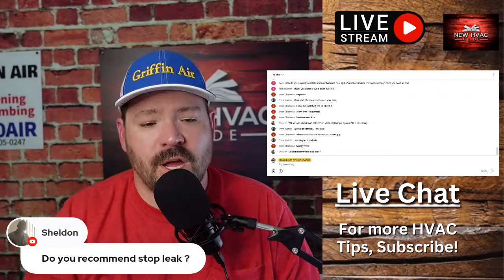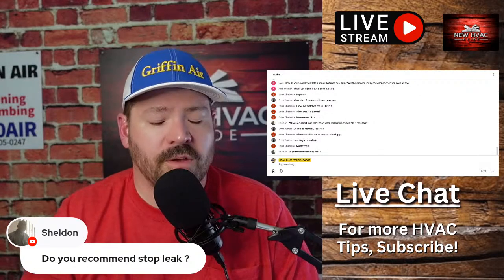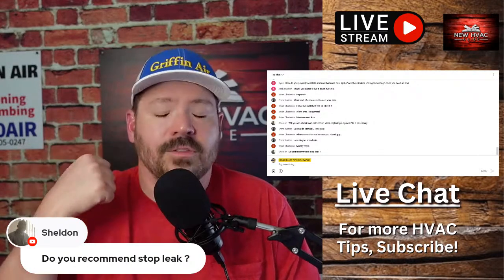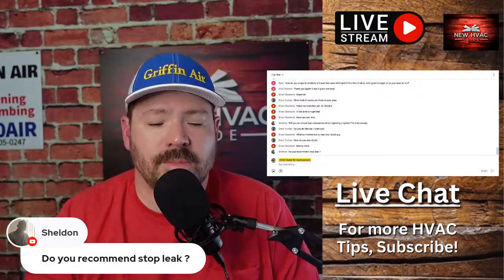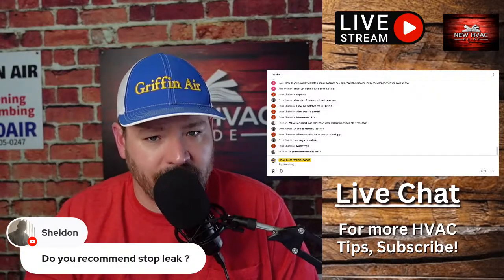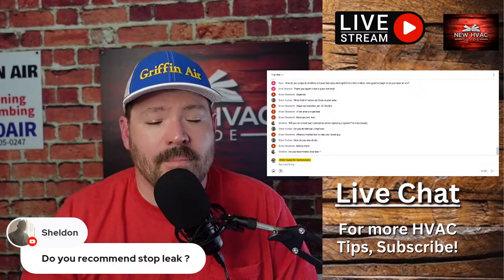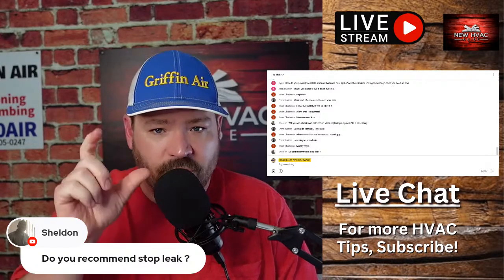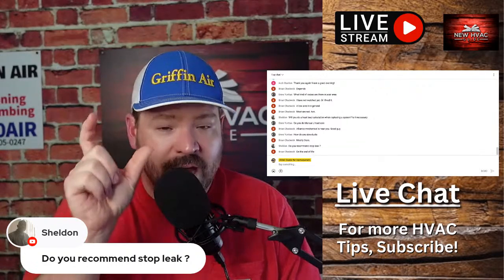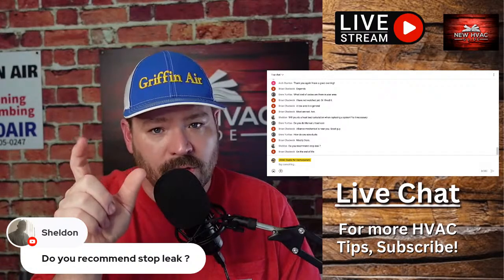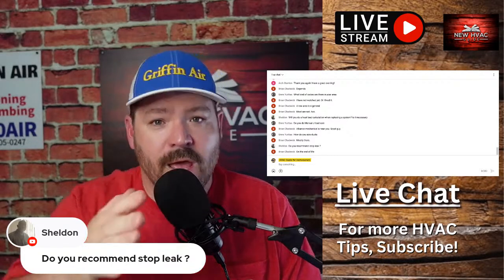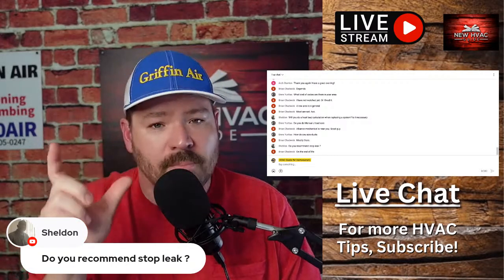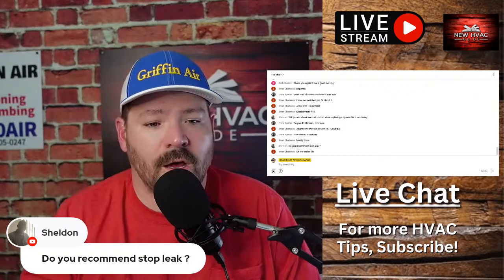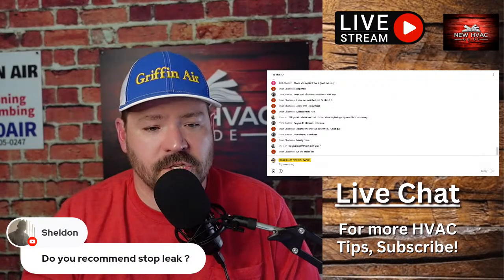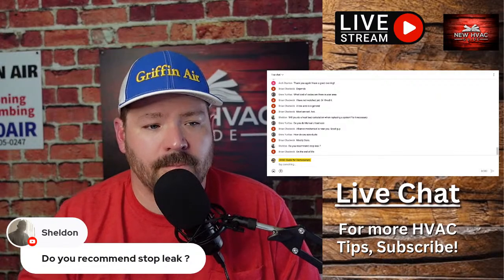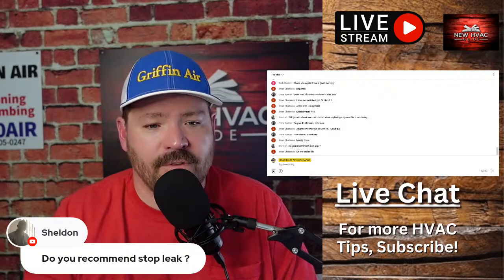I have used Stop Leak. It's not my go-to, but if I have a unit on its last leg and they're just trying to get a little more life out of that system, and it's got a very, very small leak, meaning I'm not having to add refrigerant within a 12-month window. If I am, Stop Leak's not going to work. If I have to add refrigerant in April and then again in June, Stop Leak ain't going to work, the leak's too big. But I have added it to systems to get them through if they're trying to get a little more life out of it.